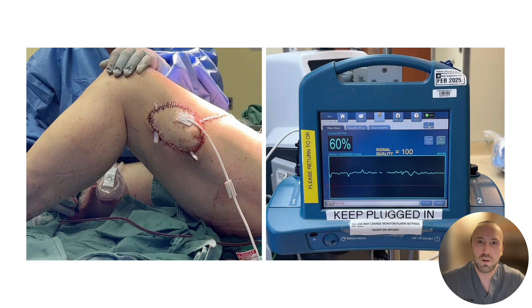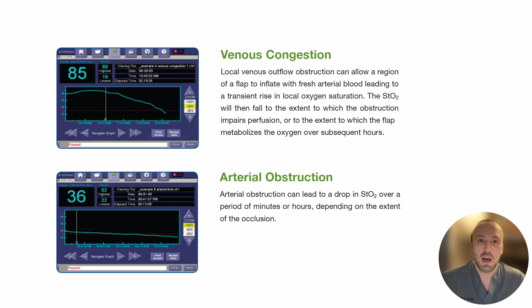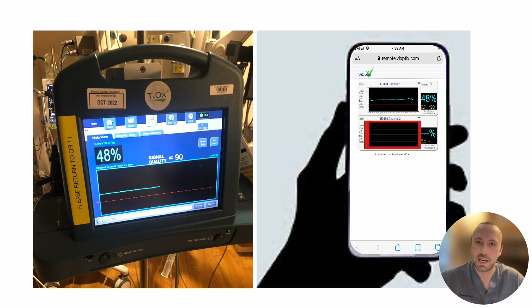However, because of this sensitivity, direct or bright lighting on the sensor probe may cause errors or changes in the oximetry and signal quality. Again, with ViOptix, we are not looking for an absolute value or level for percent tissue oxygenation, but rather a relative change or trend over time. These trends can give us information about any underlying causes of changes in flap perfusion. One of the advantages of ViOptix is the ability to remotely monitor via smartphone or computer. If alarms are triggered, the surgeon is immediately notified via text message.